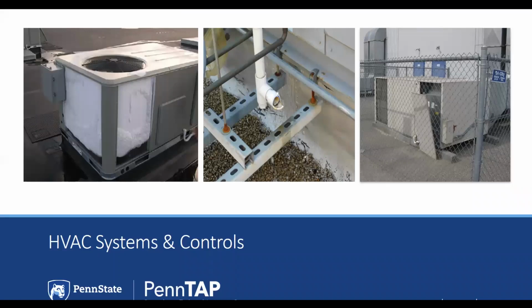After you have investigated the building's envelope, you want to take time to look at individual operating systems and review their current conditions as well. For HVAC, problems can occur in any number of the components: economizers, improper refrigerant levels, fans running during unoccupied hours, fans cycling on or off when requiring ventilation. Also check for low airflow. Zone changes may have happened. Multiple thermostats might now be overlapping due to a remodel or doors being opened.